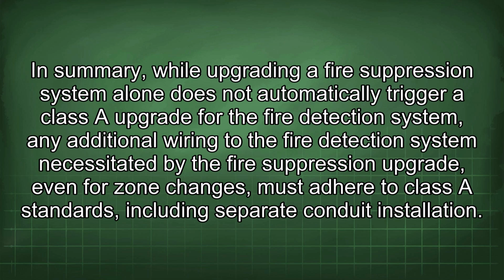In summary, while upgrading a fire suppression system alone does not automatically trigger a Class A upgrade for the fire detection system, any additional wiring to the fire detection system necessitated by the fire suppression upgrade, even for zone changes, must adhere to Class A standards, including separate conduit installation.